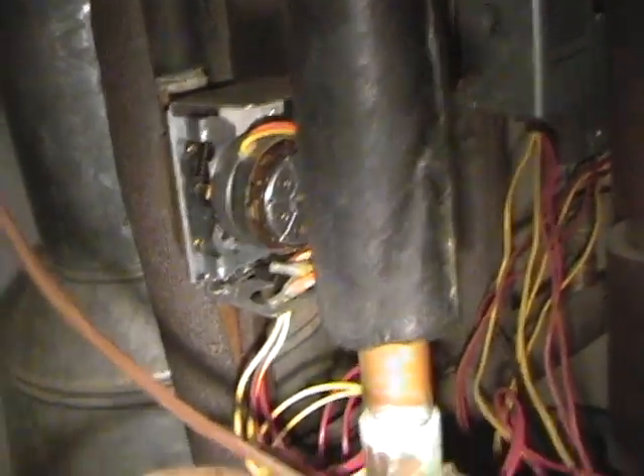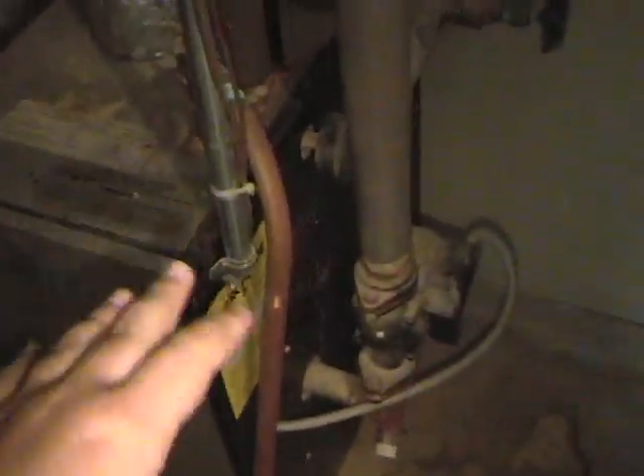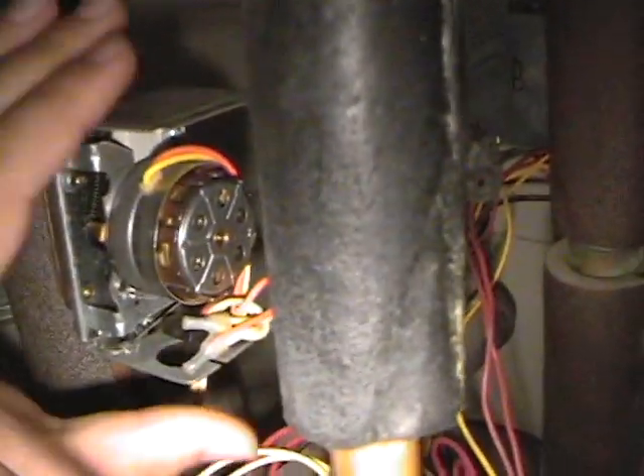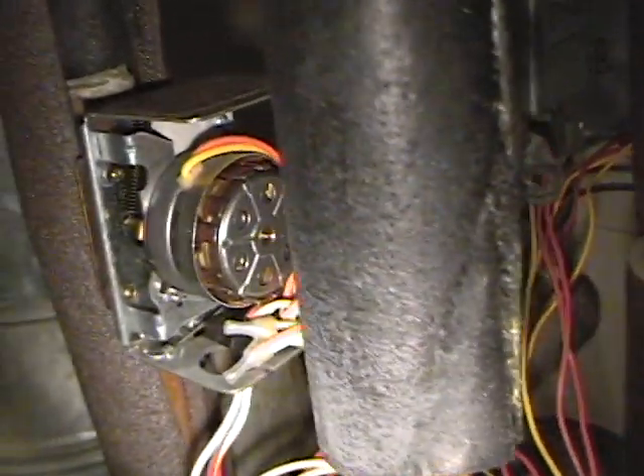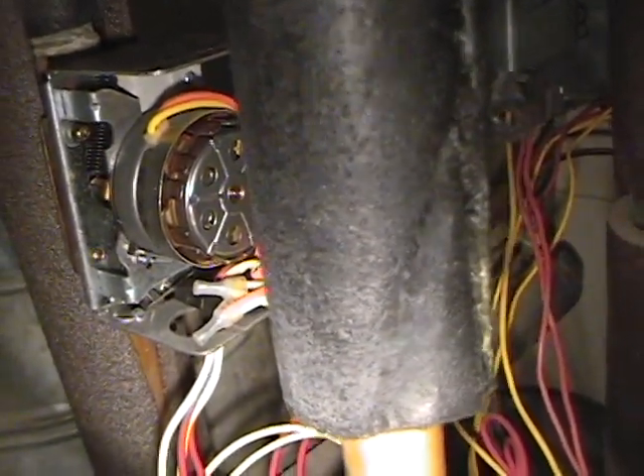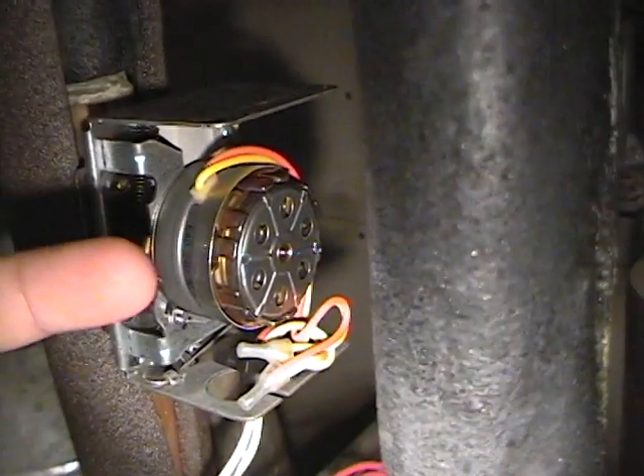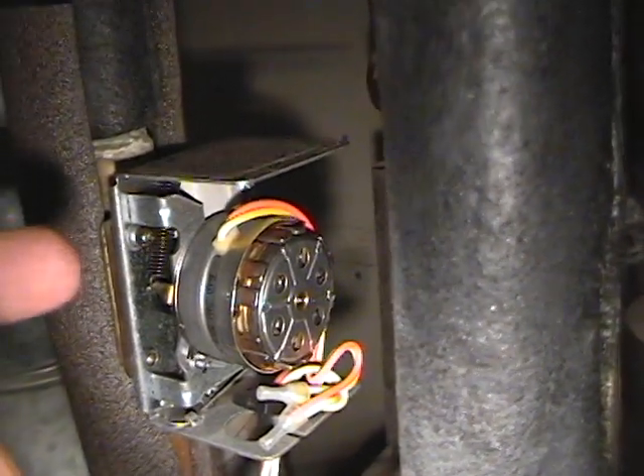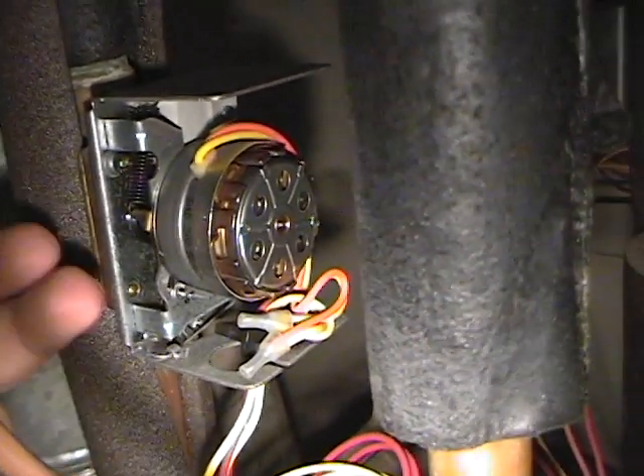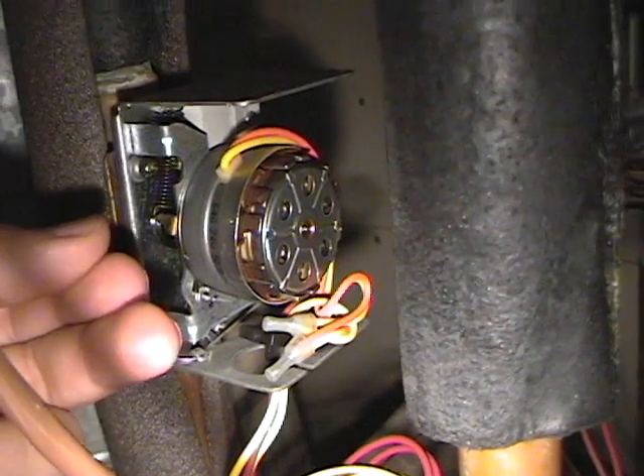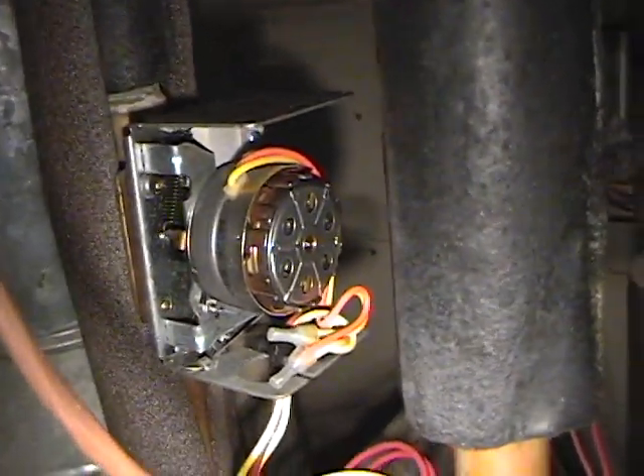There we go. And what's interesting to note is, the thermostat doesn't actually control the pump and the burner itself. It actually controls this little piece right here, the valve. And when the thermostat's calling for heat and the valve opens a certain amount, it closes an electrical contact, which then allows the boiler to turn on. It pumps the water and the burner heats the water if it has to be heated.